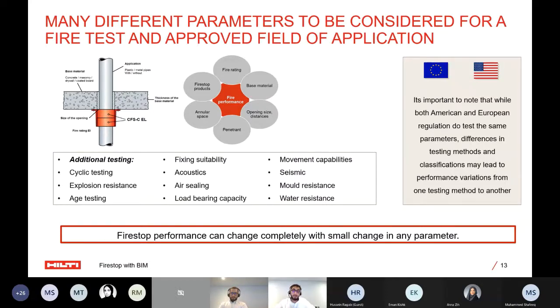So we talked about the base material, then we talk about the MEP penetration. Is it a pipe, a duct, or a cable tray? Each one will behave differently in case of a fire, and each one will need to be considered in a different manner. And even if we are just talking about pipes, we need to take into consideration, is it a combustible pipe or a non-combustible pipe? Take it one step further. So even if it's a combustible pipe, are we talking about a PVC pipe, HDPE, or PPR? Because all of them have different reactions to fire and different rates of combustibility.